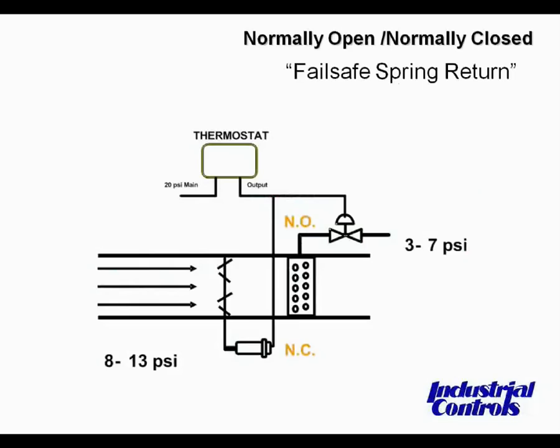Next we're going to talk about the fail-safe spring return positions. Because there is a spring in every pneumatic control device, the device will return to one end of its stroke upon system pressure loss. That position is termed the fail-safe position. It can either be normally open or normally closed, depending on the desired action. Shown here in this simplified drawing is a heating valve whose fail-safe position is in the normally open position to the heating coil, and an outside air damper actuator whose fail-safe position is normally closed.